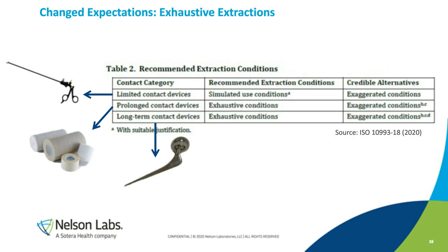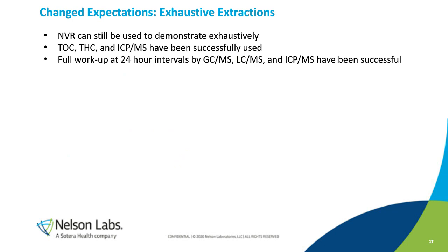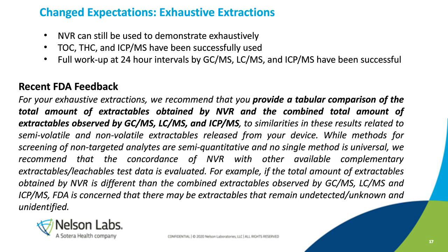Exhaustive extractions with the 3 solvents are recommended for prolonged and long-term contact devices. Limited contact devices, at least in the standard, have a lighter recommendation, with either simulated use or exaggerated conditions. I think the expectation within the FDA is that these extractions should be conducted exhaustively. It's one of those things that we've pushed back on a lot over the past 2 years.